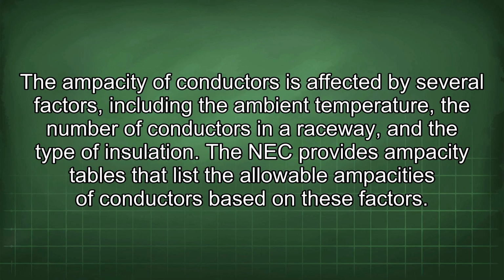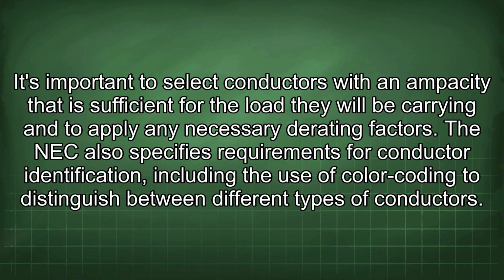The ampacity of conductors is affected by several factors, including the ambient temperature, the number of conductors in a raceway, and the type of insulation. The NEC provides ampacity tables that list the allowable ampacities of conductors based on these factors. It's important to select conductors with an ampacity that is sufficient for the load they will be carrying and to apply any necessary derating factors.